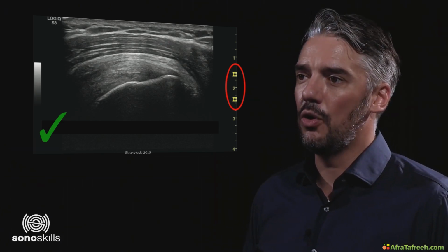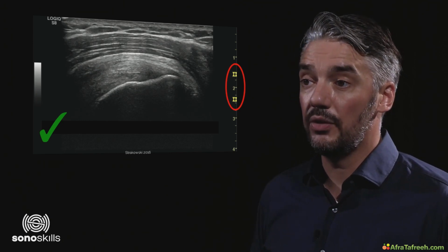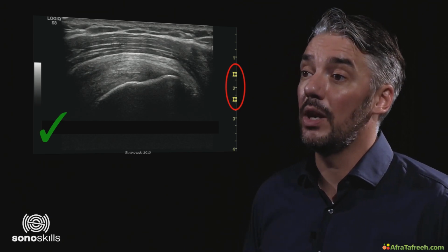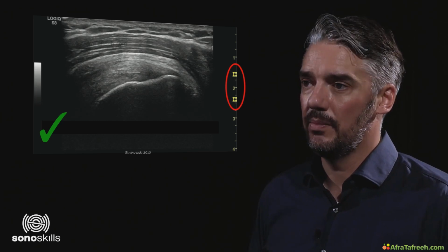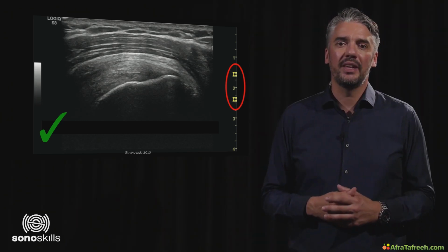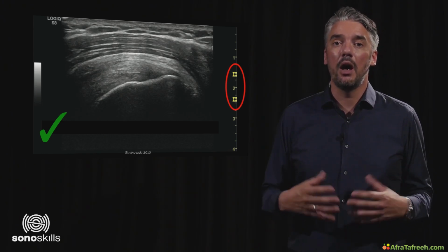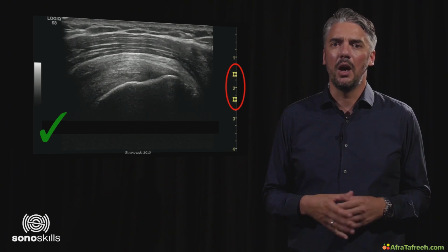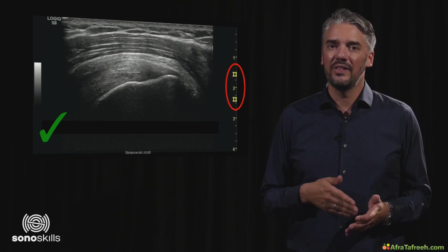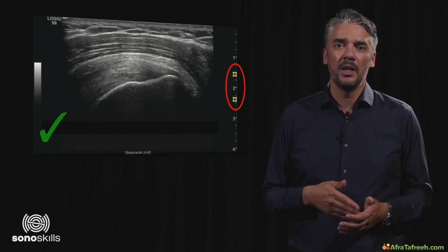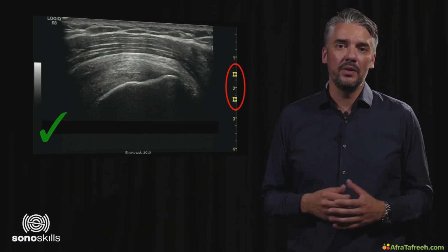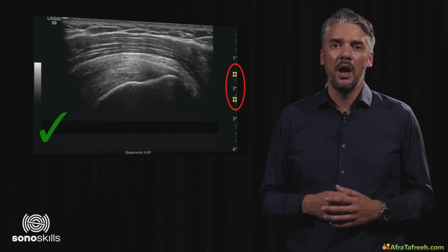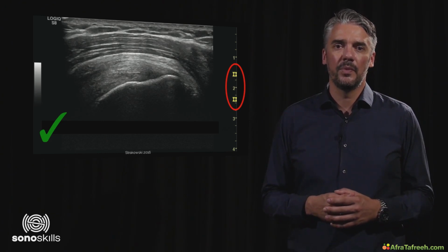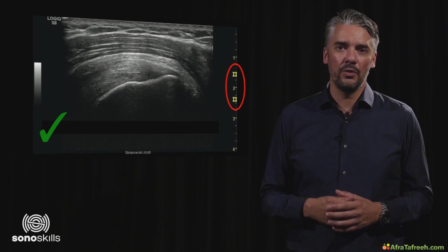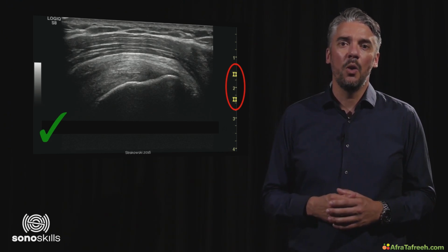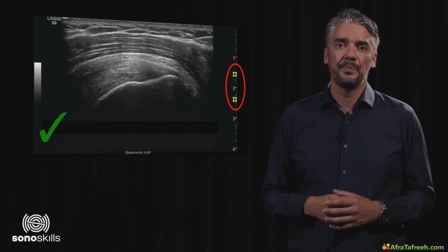Failure to maintain the focal zone in the proper location while scanning will result in decreased resolution at the point desired. More than one focal zone can be used if the area of interest is larger than the single horizontal level. However, additional focal zones tend to decrease the frame rate. The frame rate refers to the speed at which the image regains clarity after the transducer is moved. For this reason, too many focal zones make the image harder to see when the transducer is moved rapidly.